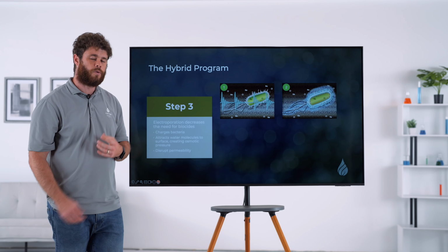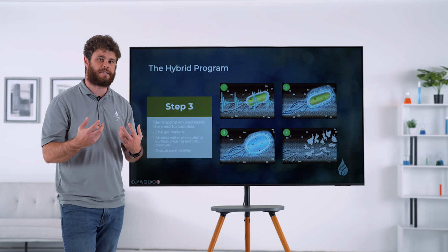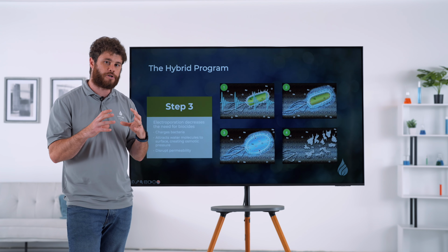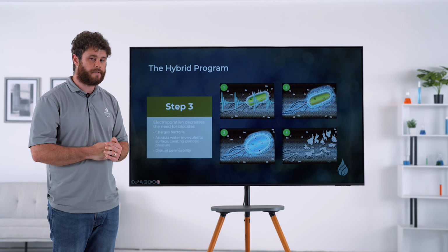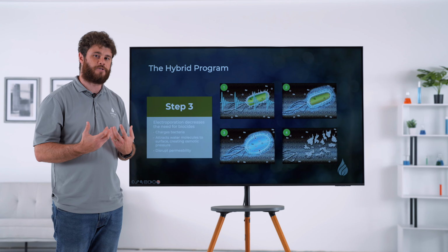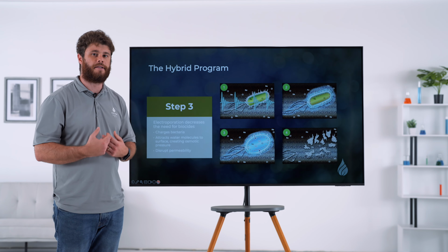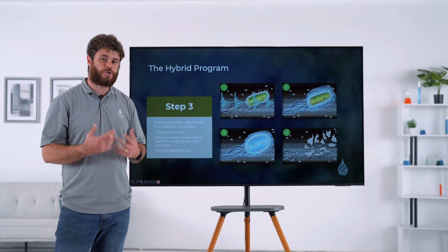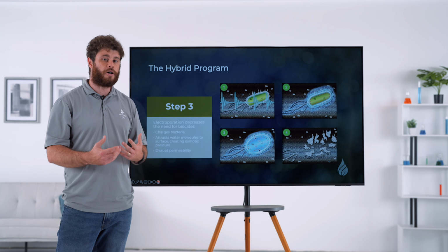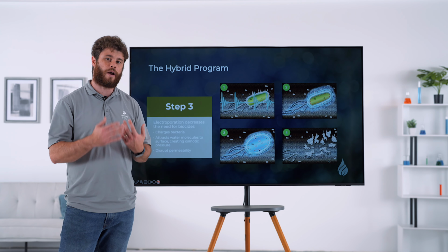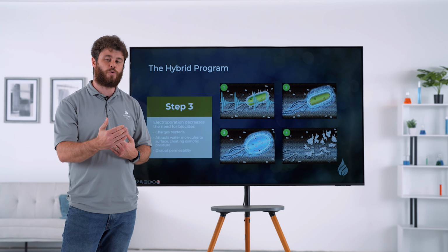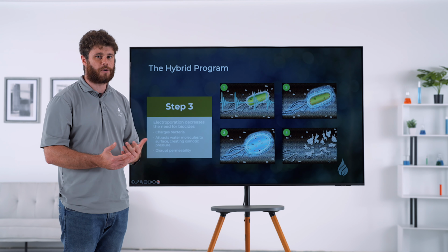Lastly, bacteria. When we charge the bacteria cells that are getting passed through the system, as that pure layer of water is settling on the cell's membrane, it's going to slowly force its way in through osmotic pressure and cause the cell to burst and die. So instead of using biocides and corrosion inhibitors and scale inhibitors to control the system, we're utilizing this oscillating coaxial magnetic field that will charge the scaling ions, utilize current to control for corrosion, and charge the bacteria cells to control for bacteria. Because we're not relying on the chemicals to control this system, we're able to increase our cycles of concentration to 2x what they were before. Now we still will feed supplemental chemicals for this program, typically around 20% of what you were once feeding, but the water savings and chemical savings speak for themselves.